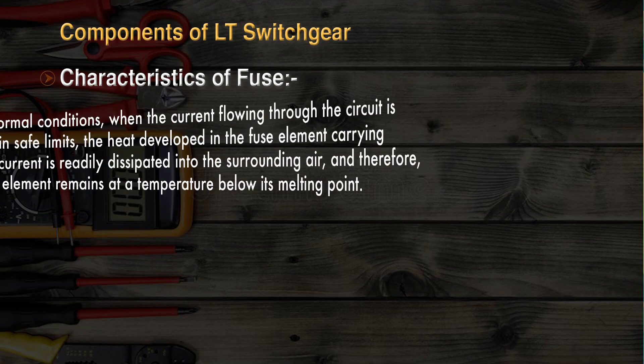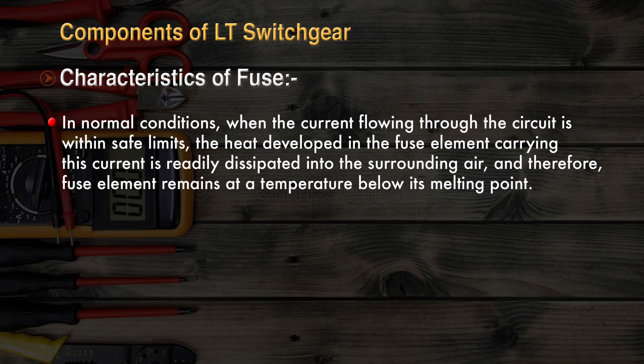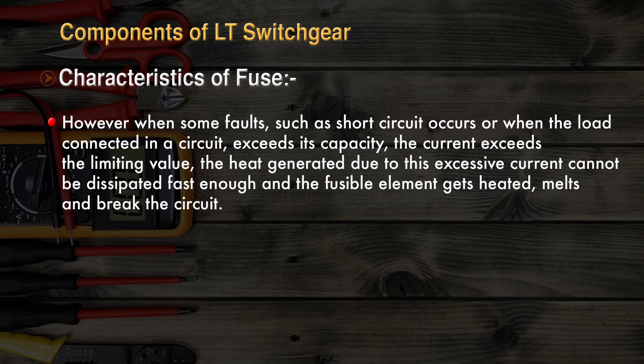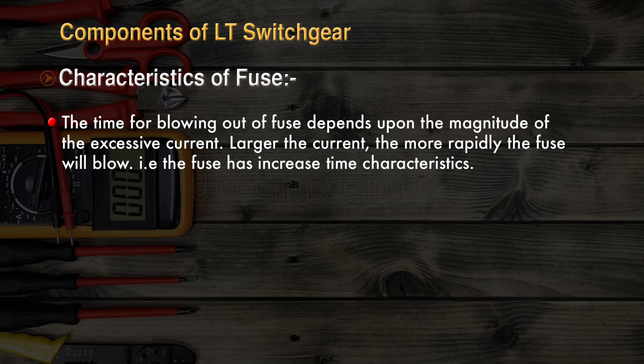In normal conditions, when current flowing through the circuit is within safe limits, the heat developed in the fuse element is readily dissipated into the surrounding air and the fuse element remains below its melting point. However, when a fault such as short circuit occurs or the load exceeds its capacity, the excessive current generates heat that cannot be dissipated fast enough, causing the fuse element to heat up, melt, and break the circuit. The time for blowing out depends upon the magnitude of excessive current — larger the current, more rapidly the fuse will blow.